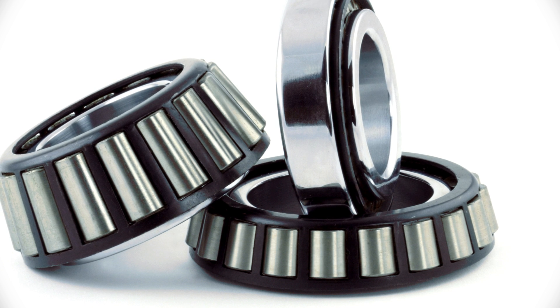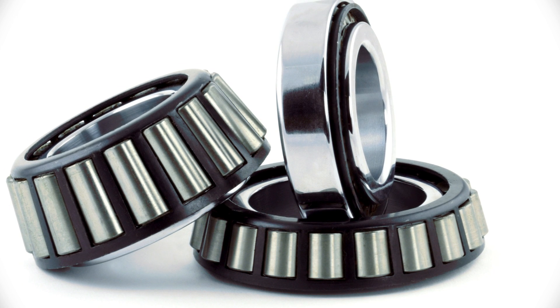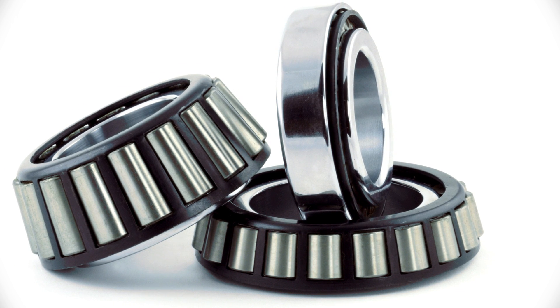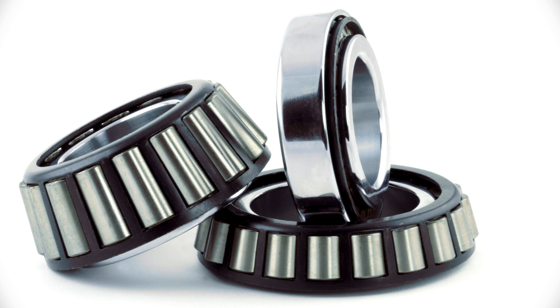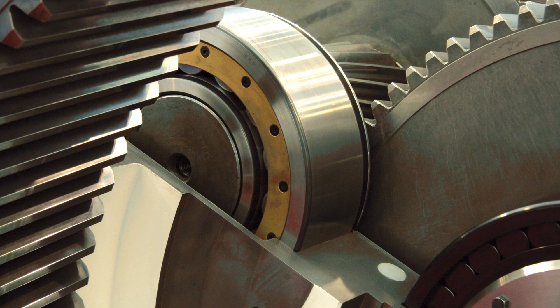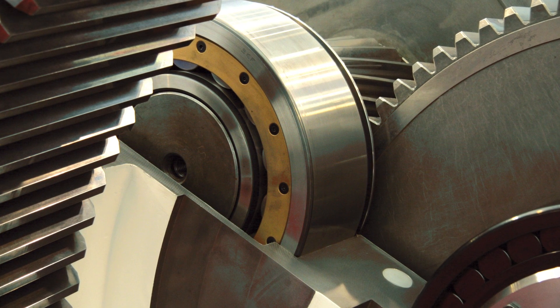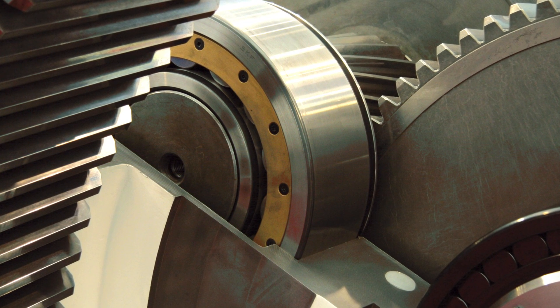Traditional mechanical bearings, like those used on the gyrobus and other simple low-speed flywheel energy storage systems, suffer from high-maintenance requirements and a dependence on high-performance lubricants to function. They're particularly sensitive to gyroscopic forces and the friction it generates. Mechanical bearings lose about 5% of a flywheel's total storage capacity per hour.